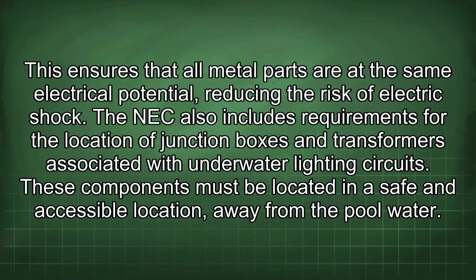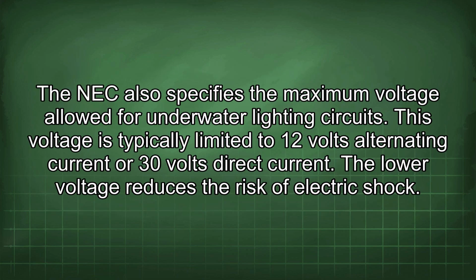The NEC also includes requirements for the location of junction boxes and transformers associated with underwater lighting circuits. These components must be located in a safe and accessible location, away from the pool water. The NEC also specifies the maximum voltage allowed for underwater lighting circuits. This voltage is typically limited to 12 volts alternating current or 30 volts direct current. The lower voltage reduces the risk of electric shock.